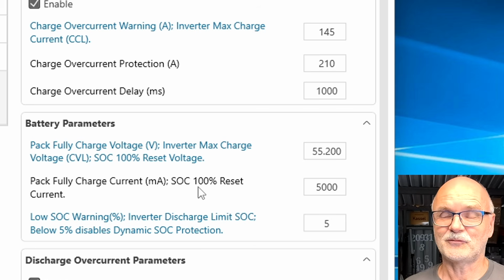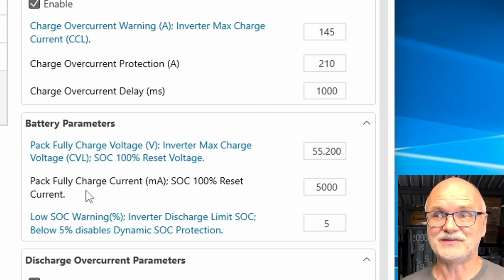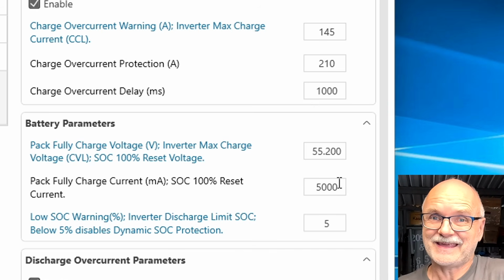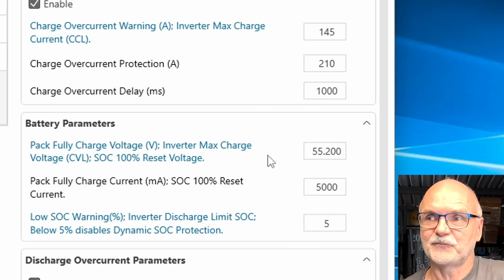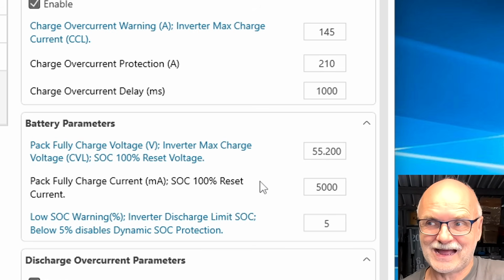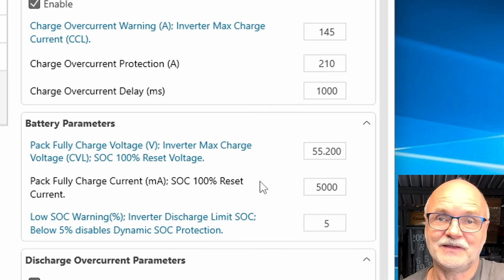But to reset the battery to 100%, you also have to meet the pack fully charged current - 5 amps here. So the battery charges to 55.2, then your current goes down all the way to 5 amps or whatever you set. It absorbs, and then the BMS resets to 100%. This is the same mechanic as we have seen before with the PACE BMS - there's always a full charge voltage and a full charge current you can set to reset your BMS to 100%.